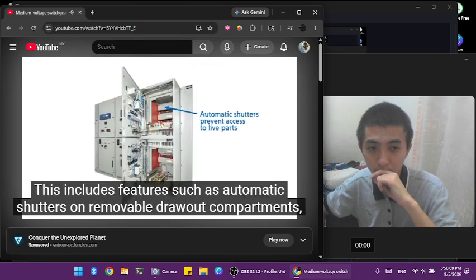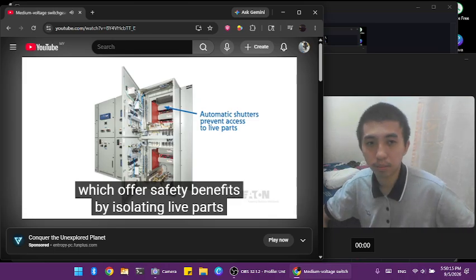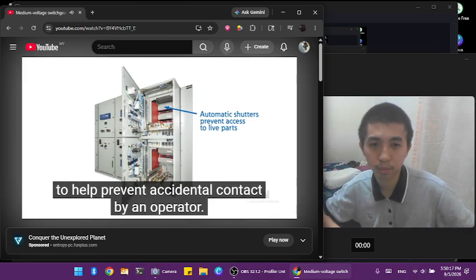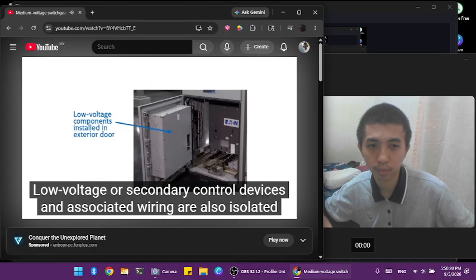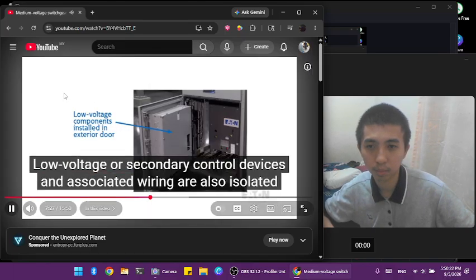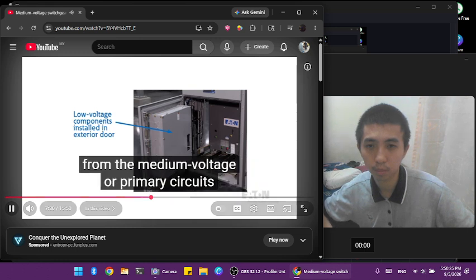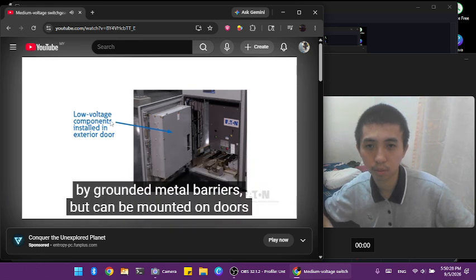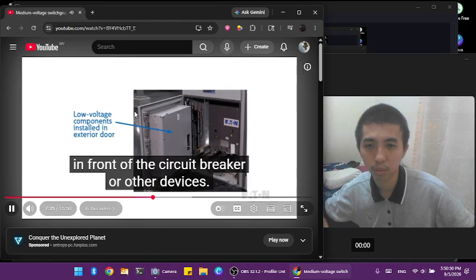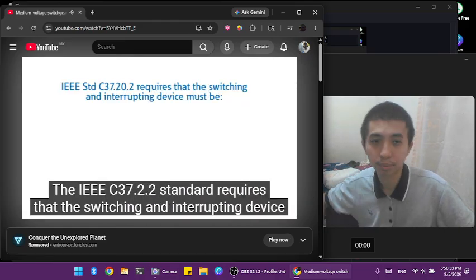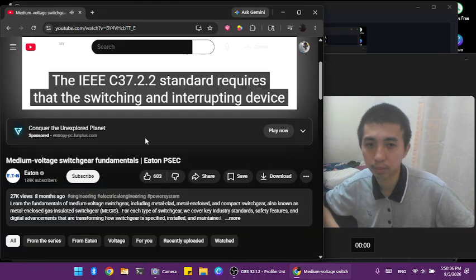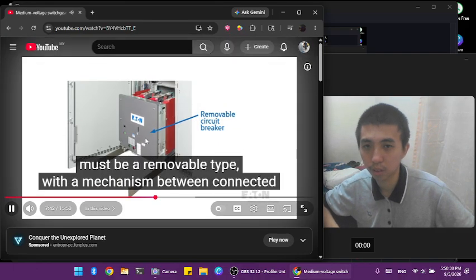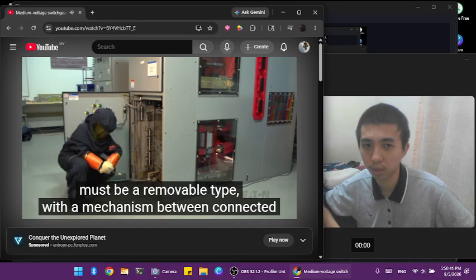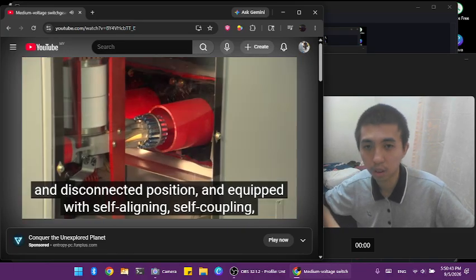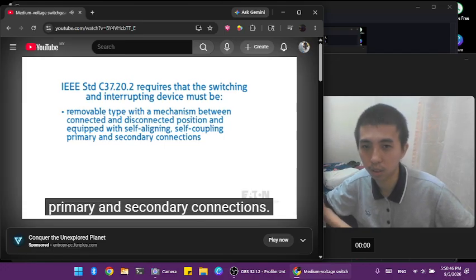This includes features such as automatic shutters on removable draw-out compartments, which offers safety benefits by isolating live parts to help prevent accidental contact by an operator. Low voltage or secondary control devices and associated wiring are also isolated from the medium voltage or primary circuits by grounded metal barriers, but can be mounted on doors in front of the circuit breaker or other devices. The IEEE C37.20.2 standard requires that the switching and interrupting device must be a removable type with a mechanism between connected and disconnected position, and equipped with self-aligning, self-coupling, primary and secondary connections.